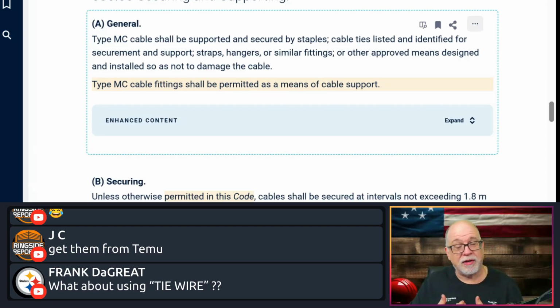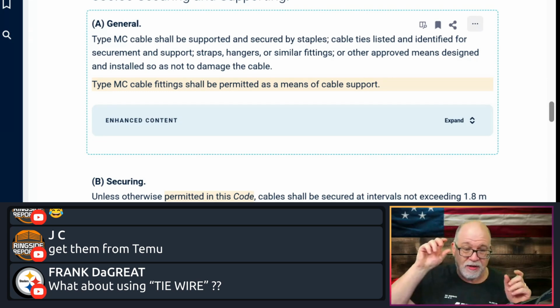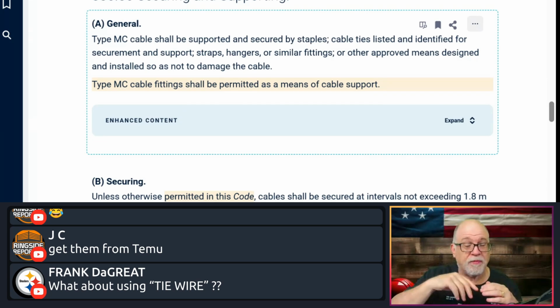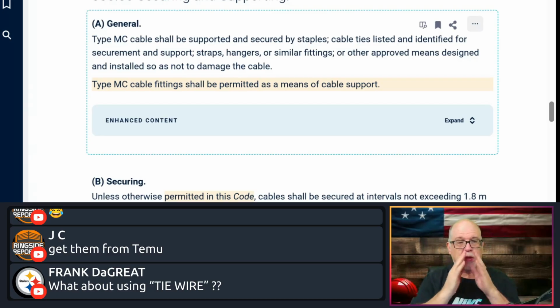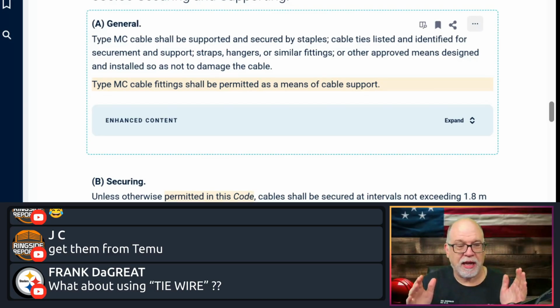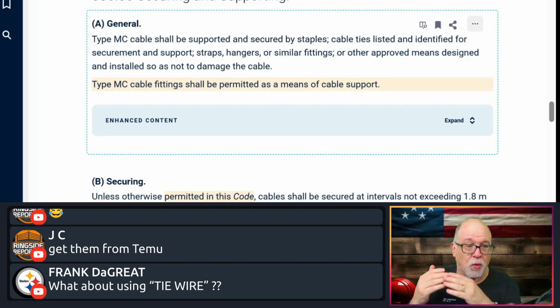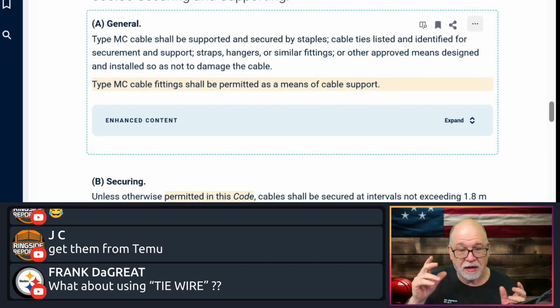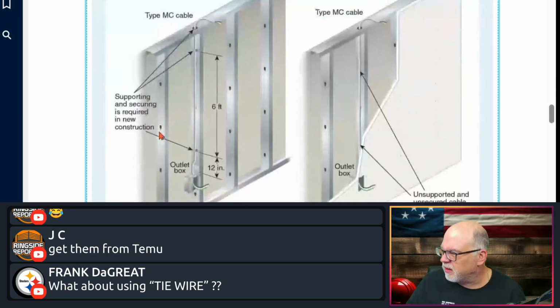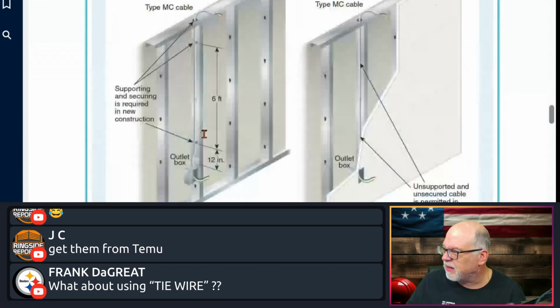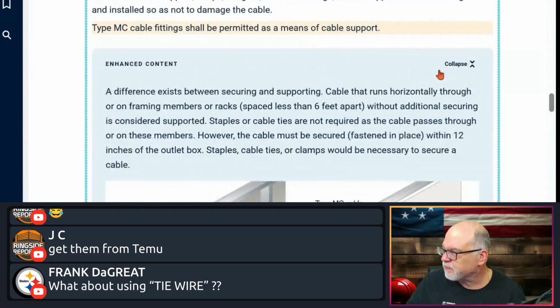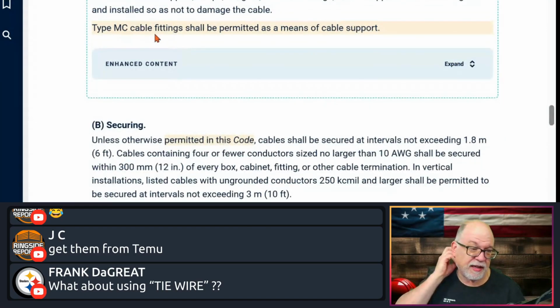So that's why it's important to make this statement, because there are many people that say, well, I got a fitting and I got this 6-foot whip of unsupported cable. They go, oh my, I need you to put a strap in there. And you're like, no, it is considered supported at the box, that type of thing. Anyway, they don't really give any example of that scenario. But again, a cable fitting, and we'll see what we're talking about here in a minute.